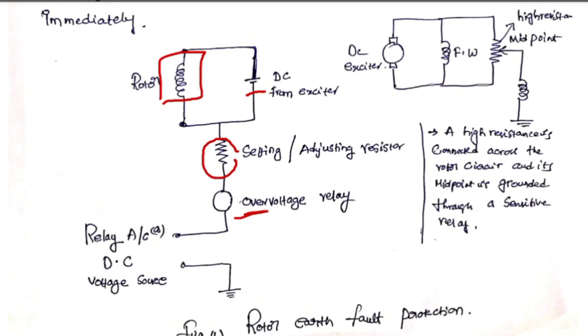You can see in this diagram the rotor, DC exciter, and field winding. The DC exciter is connected to a battery. After that, the field winding is directly connected to DC voltage — that is the excitation — and a high resistance is connected with the midpoint earthed. Here we are placing the over-voltage relay. This is the circuit diagram for rotor earth fault protection.